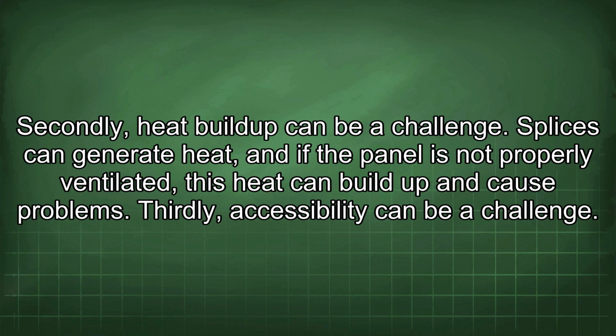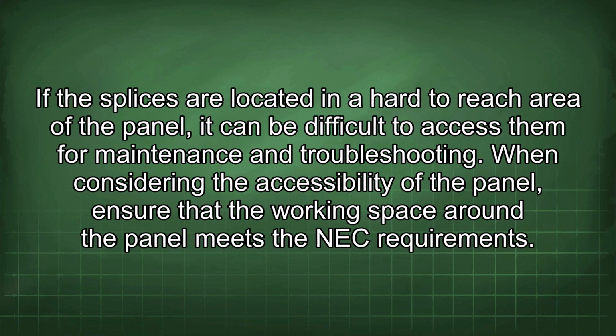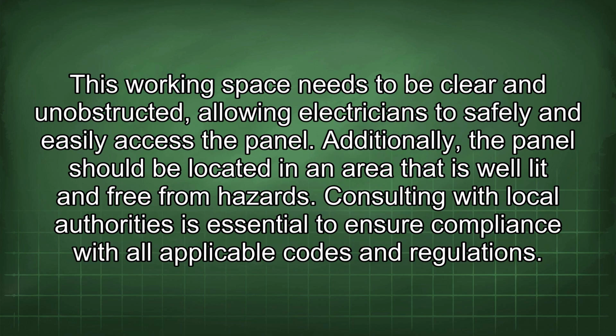Thirdly, accessibility can be a challenge. If the splices are located in a hard-to-reach area of the panel, it can be difficult to access them for maintenance and troubleshooting. When considering the accessibility of the panel, ensure that the working space around the panel meets the NEC requirement. This working space needs to be clear and unobstructed, allowing electricians to safely and easily access the panel. Additionally, the panel should be located in an area that is well lit and free from hazards.